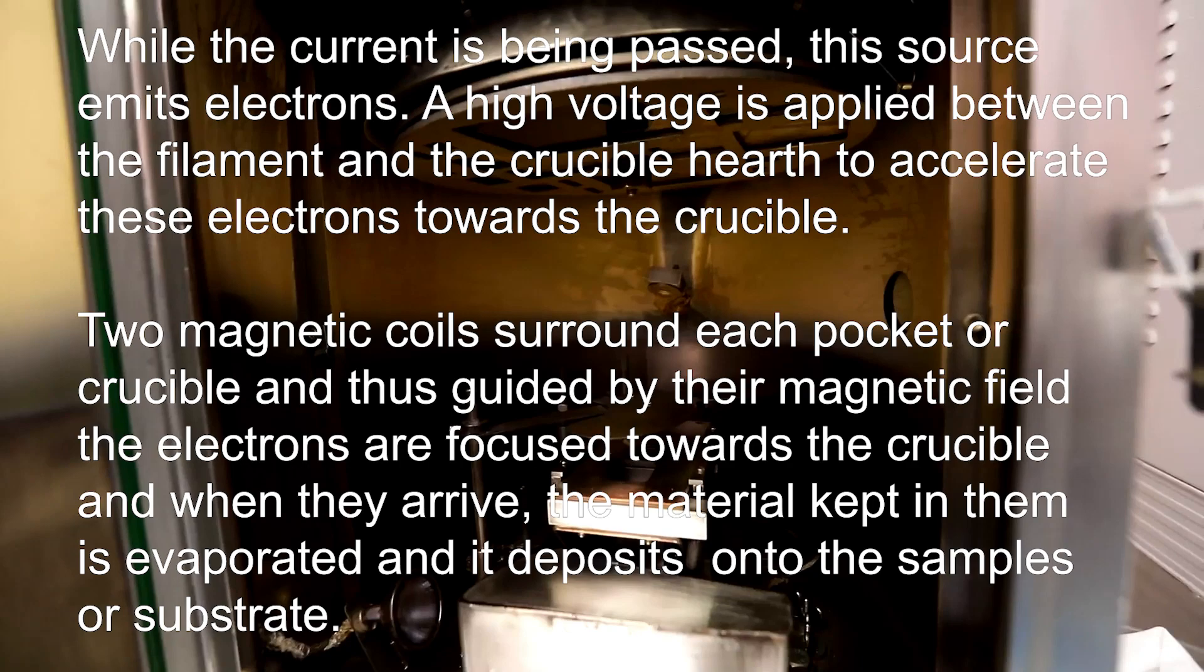Two magnetic coils surround each pocket or crucible and thus guided by their magnetic field, the electrons are focused towards the crucible. And when they arrive, the material kept in them is evaporated and it deposits onto the samples or substrate.